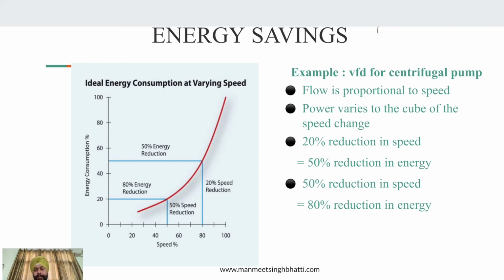So whenever you have a pump, your pump is delivering some kind of product to the plant, whether it's a chemical or water, or cooling water. The compressor is providing air. So all those things are happening. And if you see, most of the time these motors are running at full speed. Full speed means they are giving you the complete process at the highest level, so that the last point of delivery has the required pressure. That is the basic philosophy that we follow.